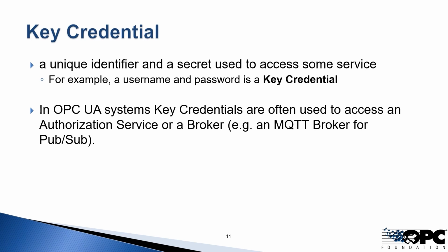So in PubSub, where we used MQTT as the middleware for the publishing, typically any entity that's going to access that broker, the broker service itself is secured, and the broker service will require some key credential to be passed to it in order to use it, and therefore the OPC publisher or subscriber would need to know that key credential. So by centralizing the management of the key credentials, again, I can update them and revise them and change them and present them and so forth in a centralized manner.